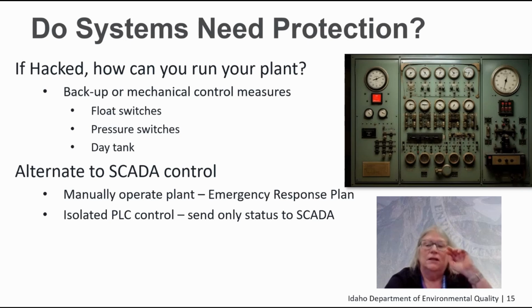One approach is what I call old school engineering. I was around back when we had relays and hardwired everything. If you have a level sensor that's a critical measurement on your plant, you could put in float switches to provide basic functionality in case you lose your level sensor. You can also put in pressure switches, either low or high pressure, to help protect your equipment.